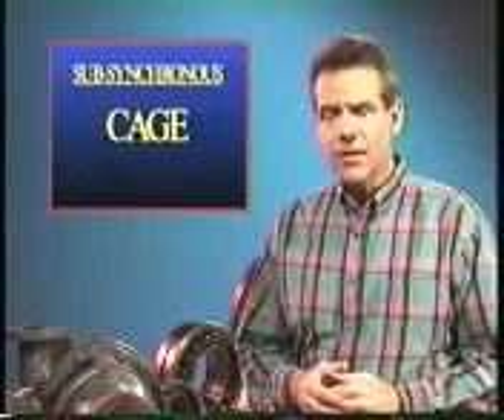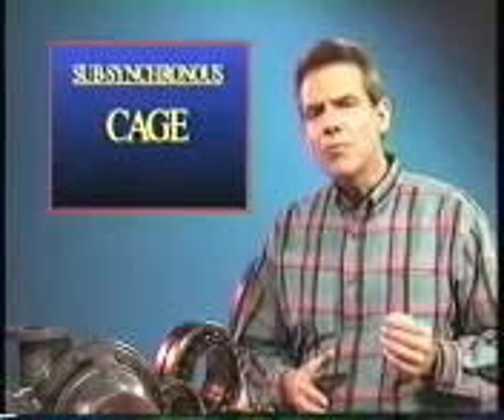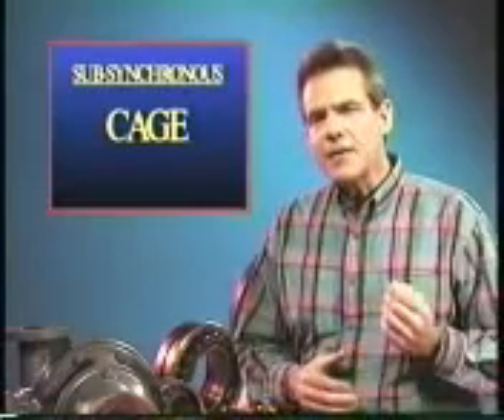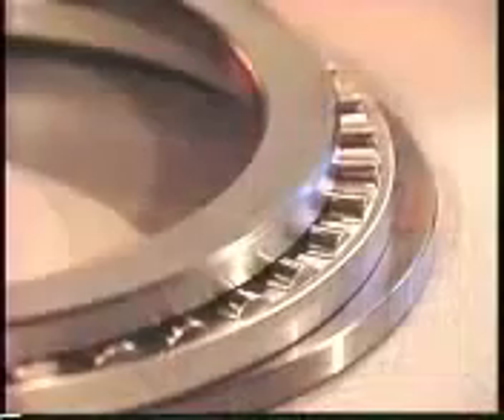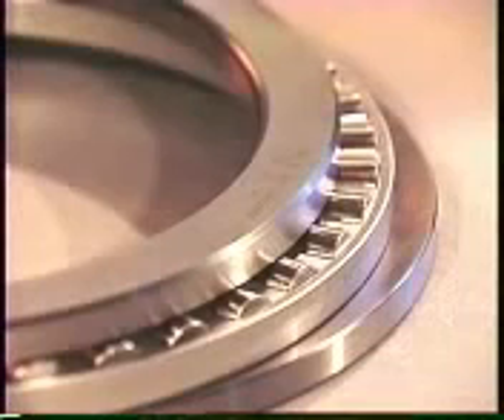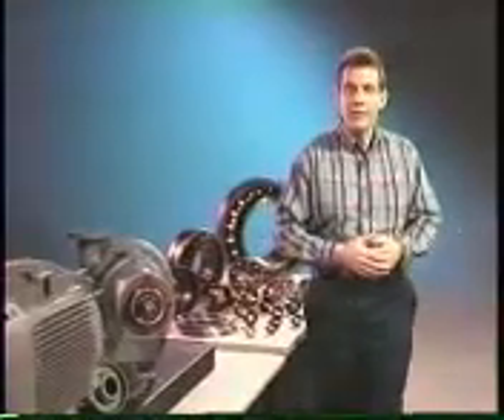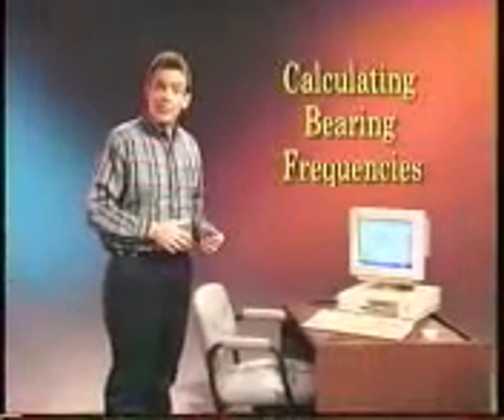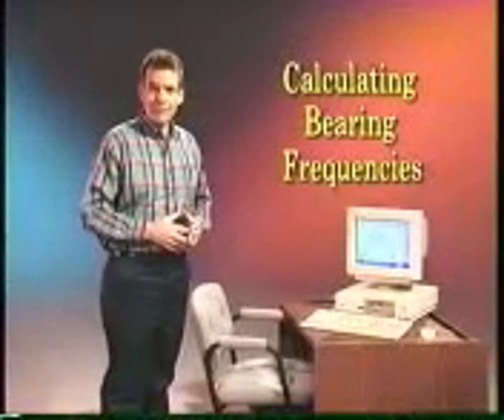The cage frequency will be less than 1/2 or 0.5 times turning speed, usually 0.3 to 0.47 times turning speed, except in that same rare occasion mentioned before, a 90-degree contact angle thrust bearing, or in an application where the inner race is stationary. All these frequencies can be determined exactly using FreqCal, the frequency calculation program in CSI's Master Trend software.